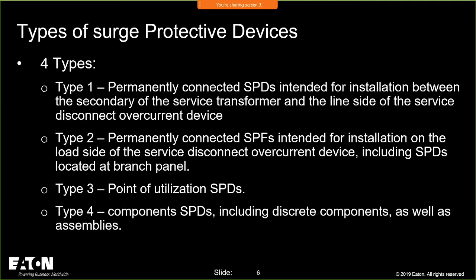There's 4 types. There's type 1, which is permanently connected, intended for installation between the secondary of the service transformer and the line side. And then there's the permanently connected, intended for installation on the load side. Type 3 is the point of utilization. And there's type 4. Remember, we said type 1 and type 2, so it could be on the line side of the service, or it could be on the load side of the service. You're not going to be leveraging a type 3, which is point of utilization, or a type 4, which is what we would typically see inside of industrial control panels and things like that.